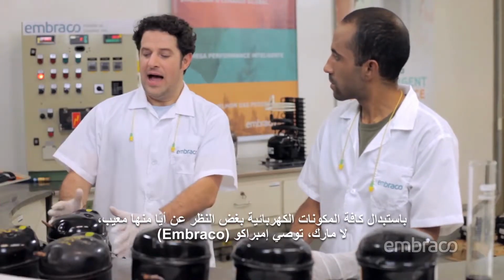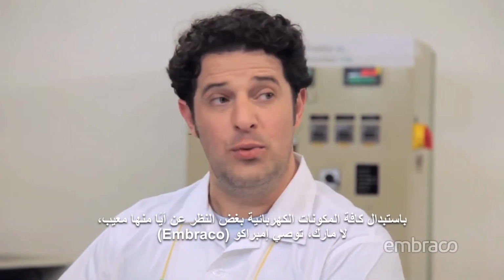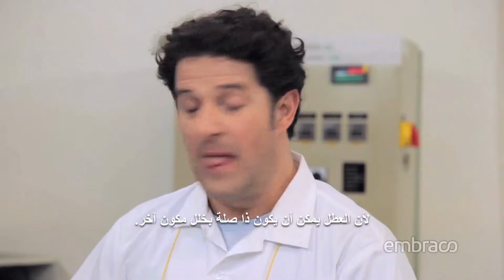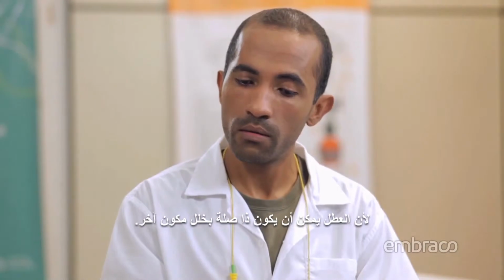No, Mark. Embraco recommends replacing all the electrical components regardless of which one of them is defective, because the failure can be linked to a malfunction of another component. Oh, and the second one here?